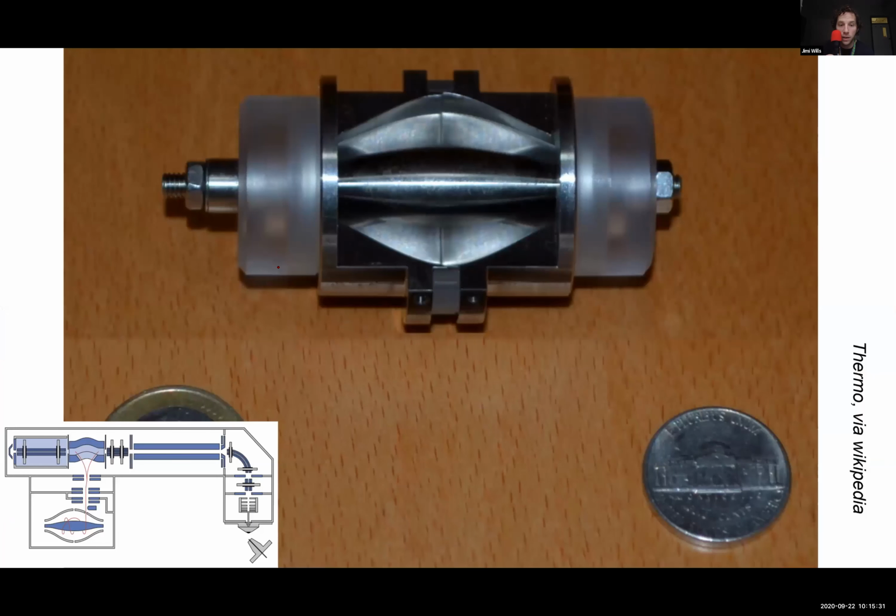And this is a vendor-made cutaway of an Orbitrap. When they make these things, it's very, very difficult to machine, and so I guess a few of them fail to make any kind of QC. And then why not cut the front off and show people what they look like inside? Anyway, the inside of this, let's say we've got positive ions coming in. The inside is negative, the outside is positive, and it causes the ions to orbit around the inside, like this.